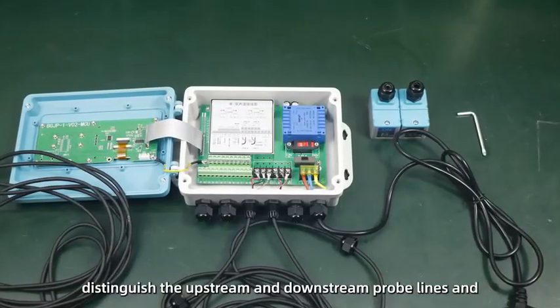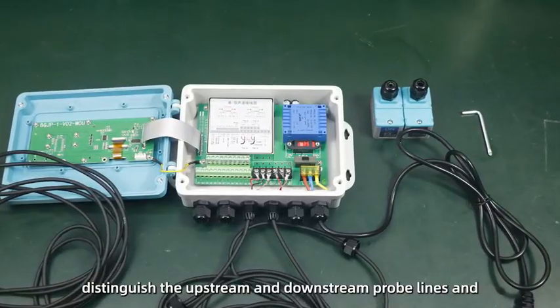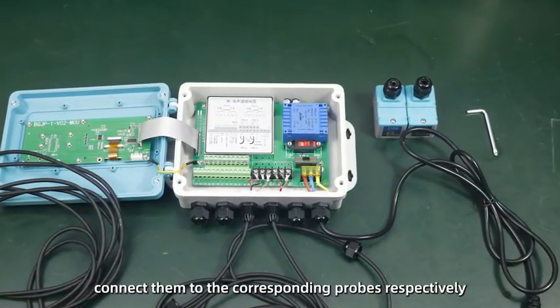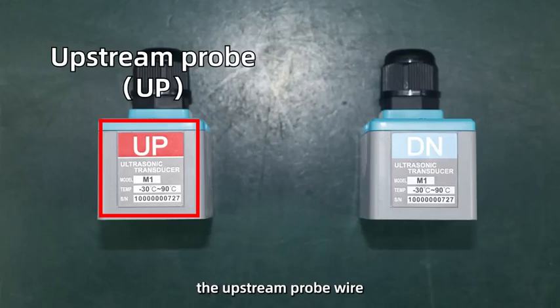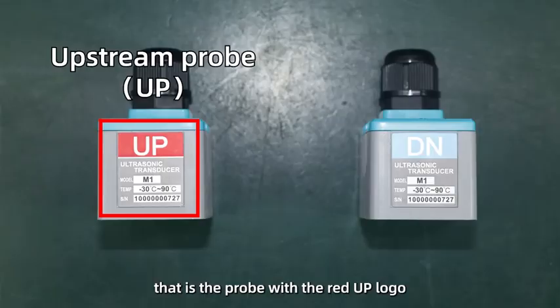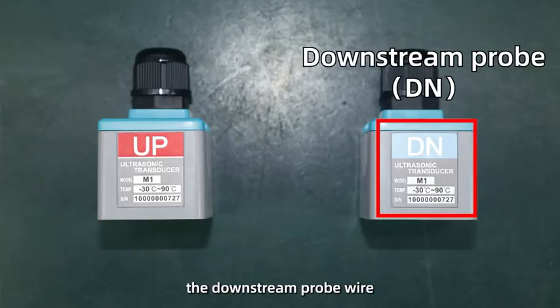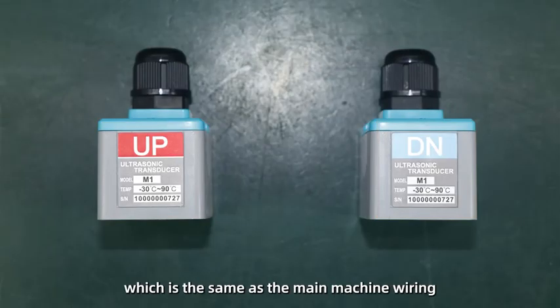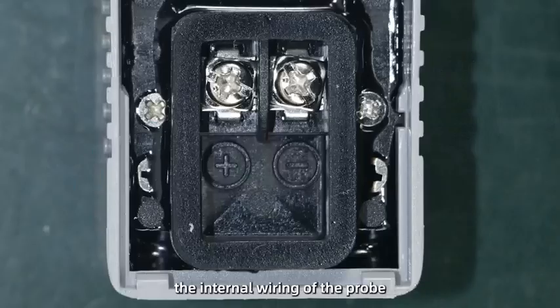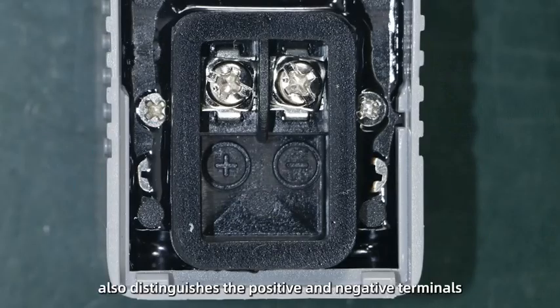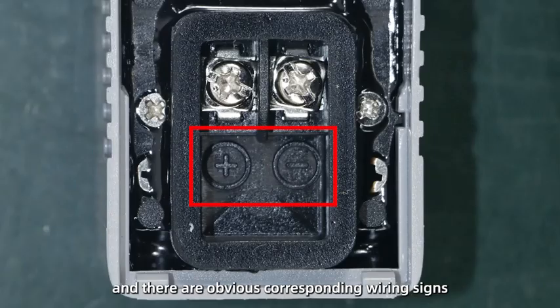Distinguish the upstream and downstream probe lines and connect them to the corresponding probes respectively. The upstream probe wire is connected with the upstream probe, that is, the probe with the red UP logo. The downstream probe wire is connected to the downstream probe, that is, the probe with the blue DN logo, which is the same as the main machine wiring. The internal wiring of the probe also distinguishes the positive and negative terminals, and there are obvious corresponding wiring signs under each terminal.